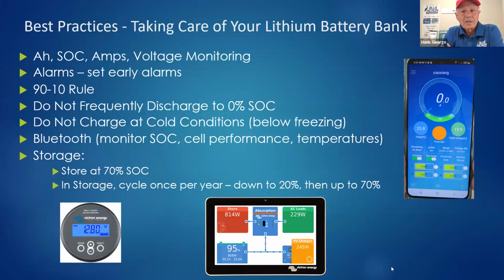Now the BMS, if it's a good BMS, will not allow you. You could try charging, forget this, and think the battery should be warm enough, you try charging. The BMS will not allow the batteries to accept charge when the cells are below freezing, below 32 degrees.